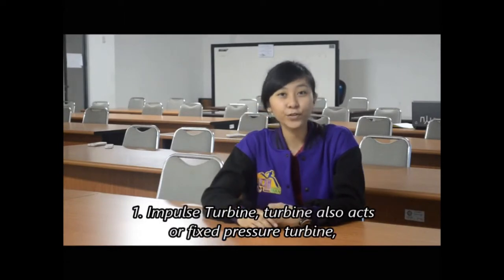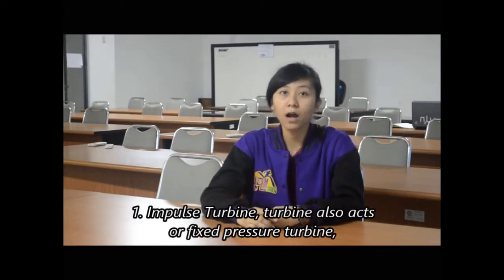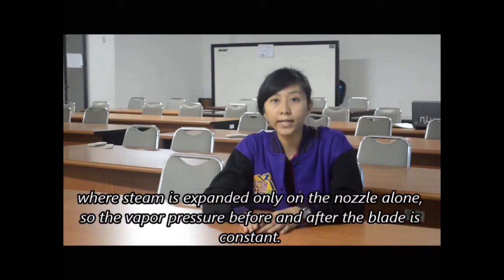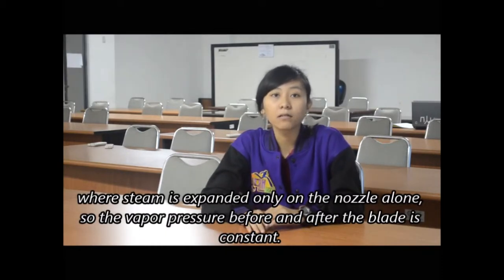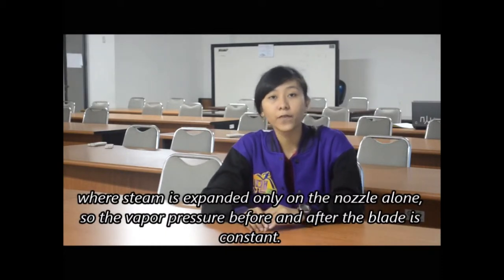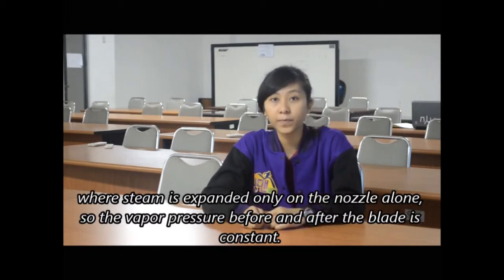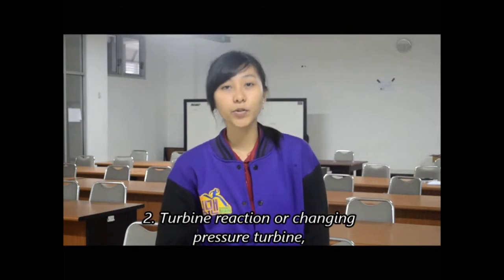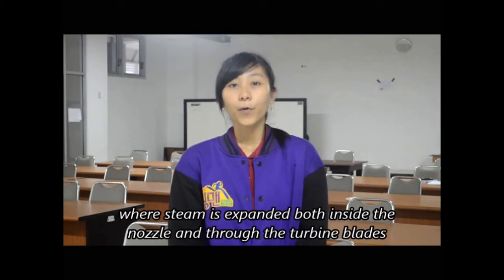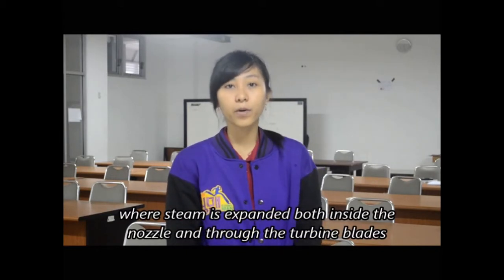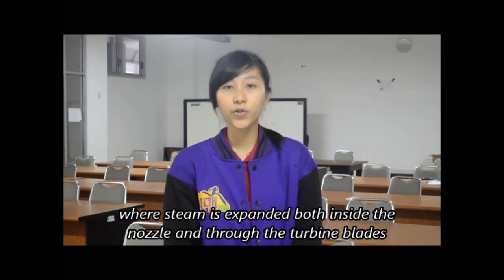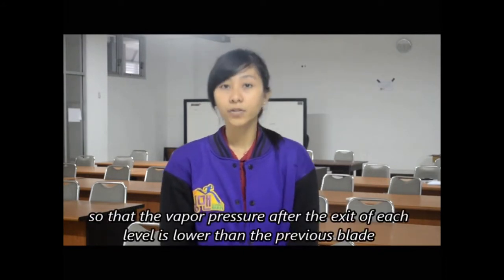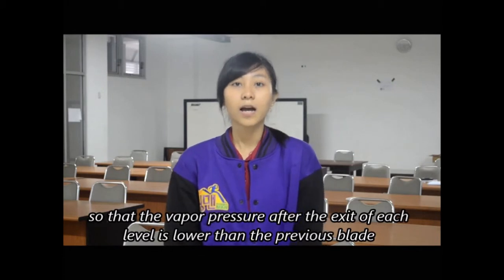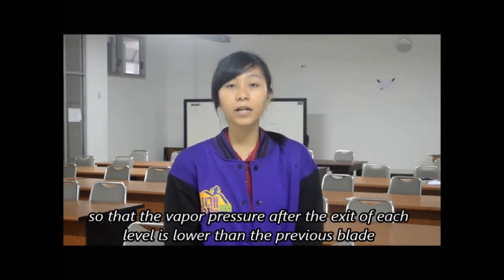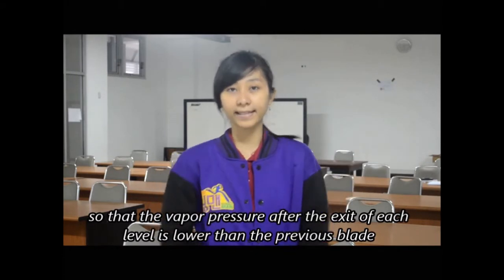1. Impulse turbine, also called a constant pressure turbine, where the steam is expanded only in the nozzle, so the pressure before and after the blade is constant. 2. Reaction turbine or pressure-compounded turbine, where the steam is expanded both inside the nozzle and through the turbine blade, so that the pressure after the exit of each stage is lower than at the previous blade.